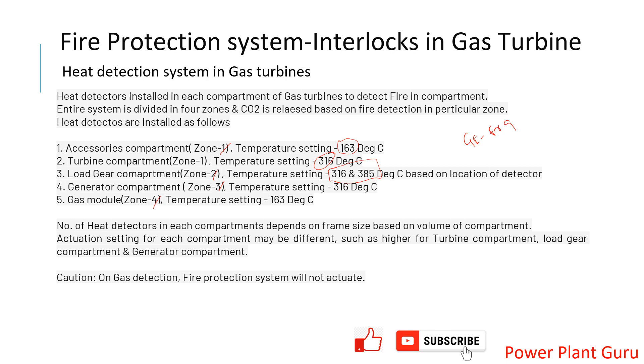For the generator compartment and gas module there is a different setting. The number of sensors per zone or compartment depends on the size and volume of the compartment. If it is a large area, you need sensors that cover the entire area; for a smaller area, one sensor may be sufficient. This allows you to monitor the temperature pattern using non-contact type thermal heat detector systems.